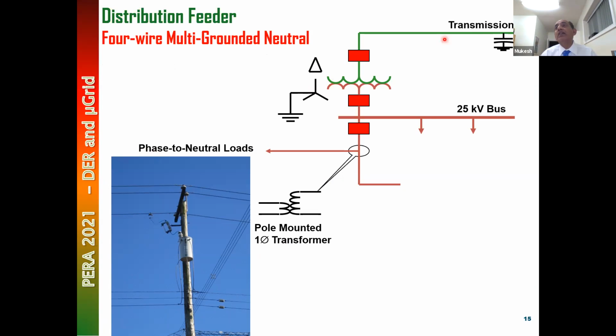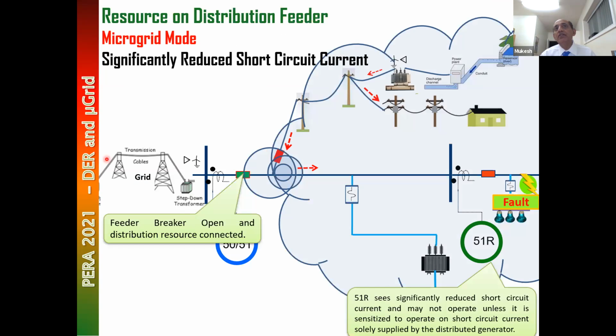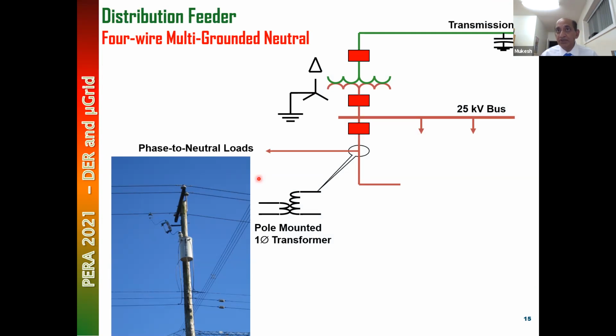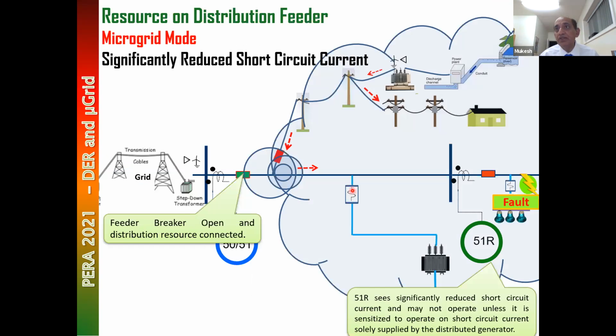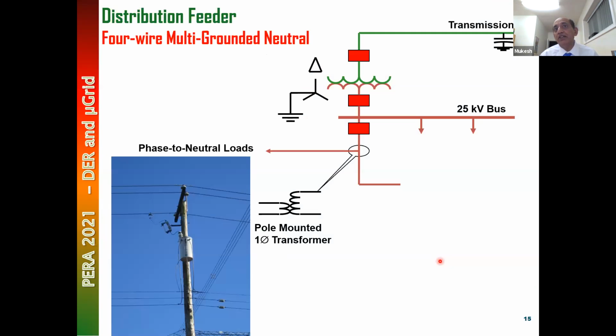What I had told you earlier: there's a transmission line that supplies a 25 kV distribution system, connected to a delta-star transformer, as I showed in the last slide. The transmission line connects to this distribution station. This is a physical representation, and this is a one-line representation of the same feeder. And this single phase transformer really looks like this. There's a three-phase feeder, three lines A, B, C, 25 kV, and there's a neutral here, a fourth wire. This is a single phase transformer connected between the phase and the neutral, and it supplies a single phase load.